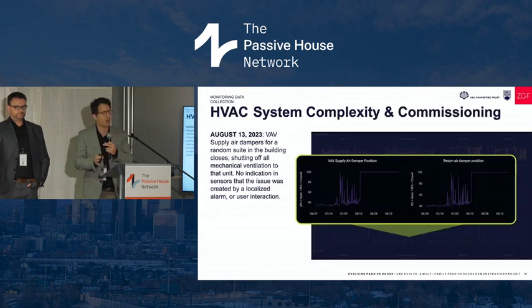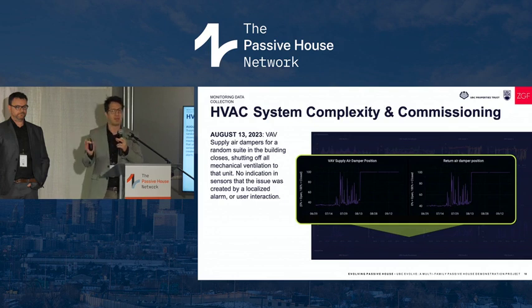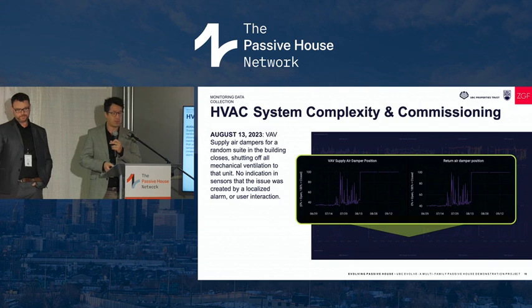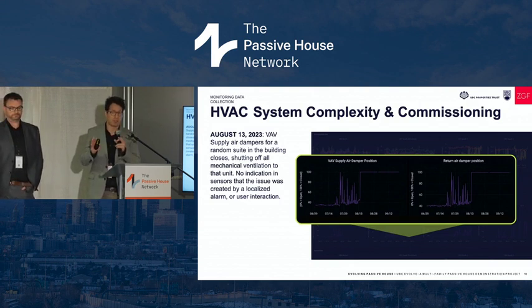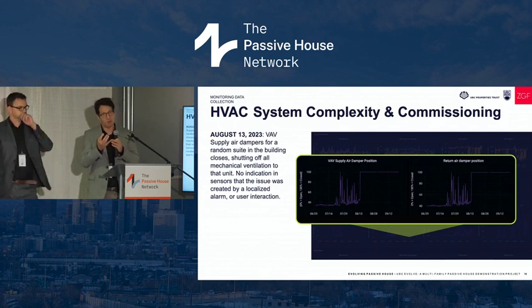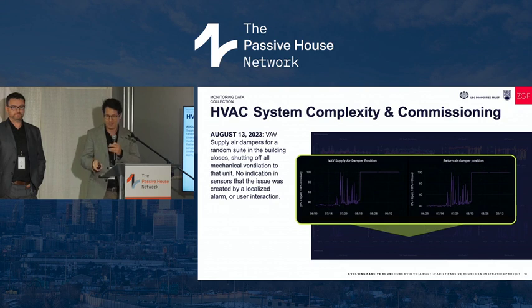Here's one anecdote. There are 110 suites in this building, and we could talk a lot about issues this building encountered in the last year. Here's one: on August 13, in one suite, the supply dampers went to a closed position randomly, meaning there might have been a reason tied to smoke alarms, temperatures, ventilation, or CO2 rates. There are about 6 levels of control, yet looking at the BMS, it's hard to tell what signaled the dampers to close. So in this one unit, the dampers closed.